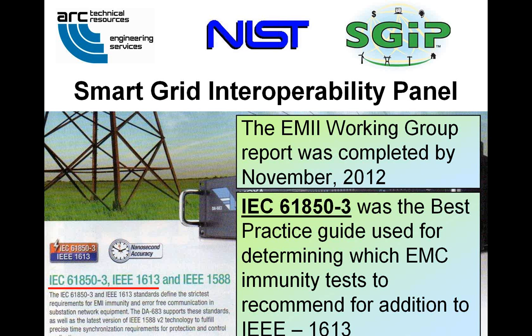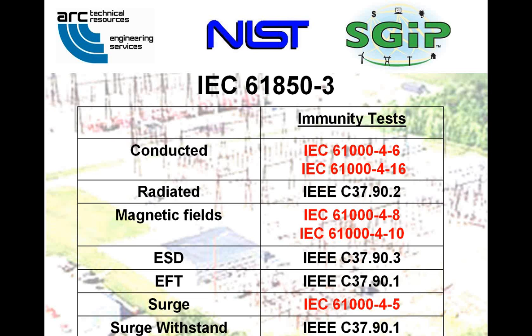61850-3 required these immunity tests, which are shown on the right, and addressed substation environments. 61000-4-6, conducted RF immunity. 61000-4-3, radiated RF immunity, which was covered here in IEEE under C37.90.2. 61000-4-8, power frequency magnetic fields. -10, damped oscillatory magnetic fields. -16, conducted common mode disturbances. 4-4 is electrical fast transient, which was already covered under C37.90.1 I mentioned earlier.